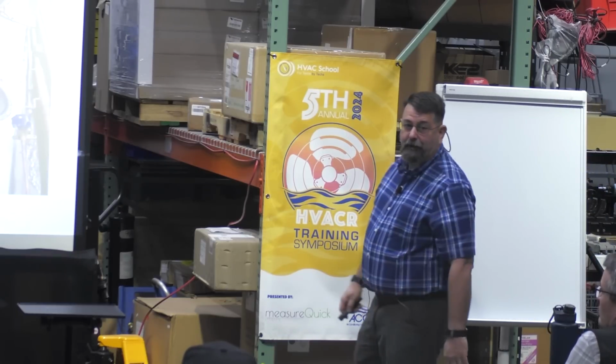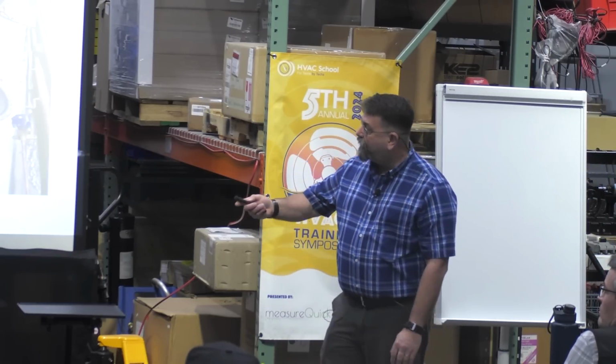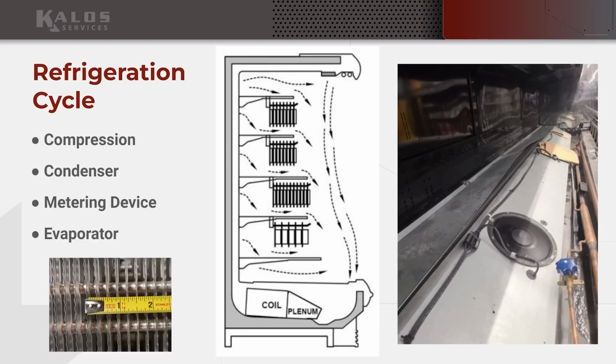Somebody violates my load limit, that's causing that supply error, right? When I say load limit, I mean they've usually, this bottom shelf is the big one, right? They stock this thing up to here, right? Well, that means my supply air is going to come down and hit that product, and it's going out on the sales floor. Now my case is negative, so it's going to make that air up, right?